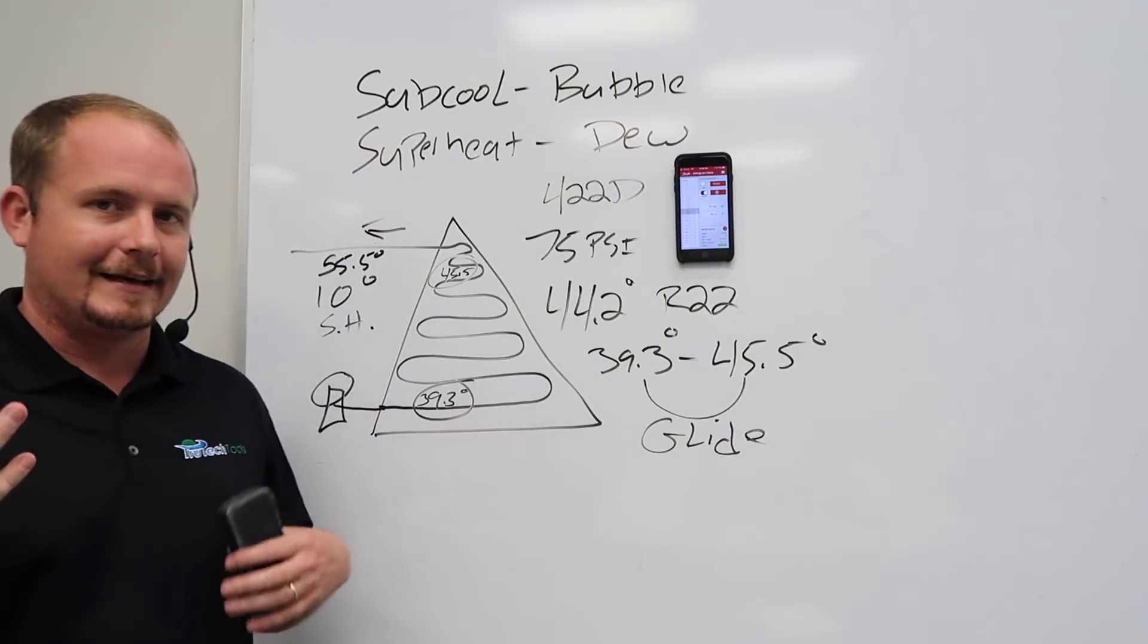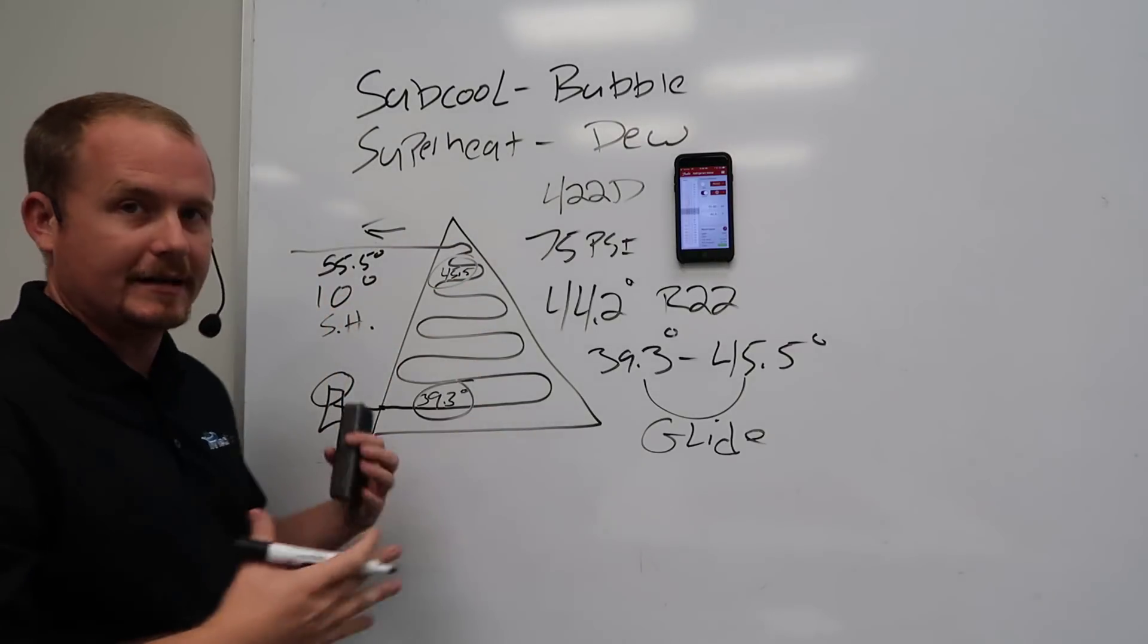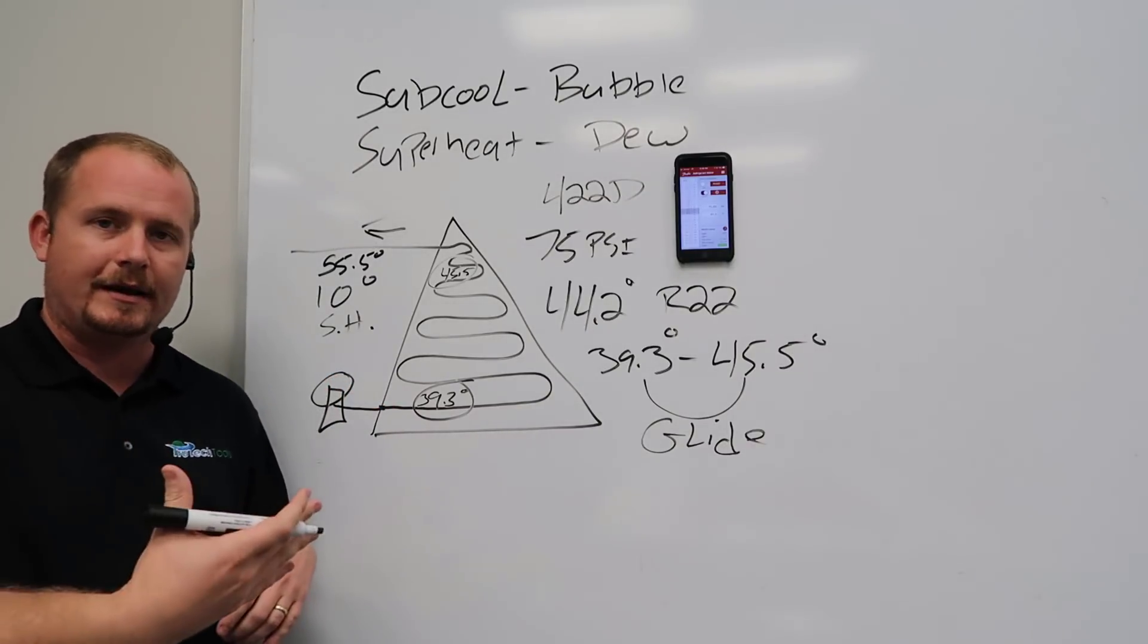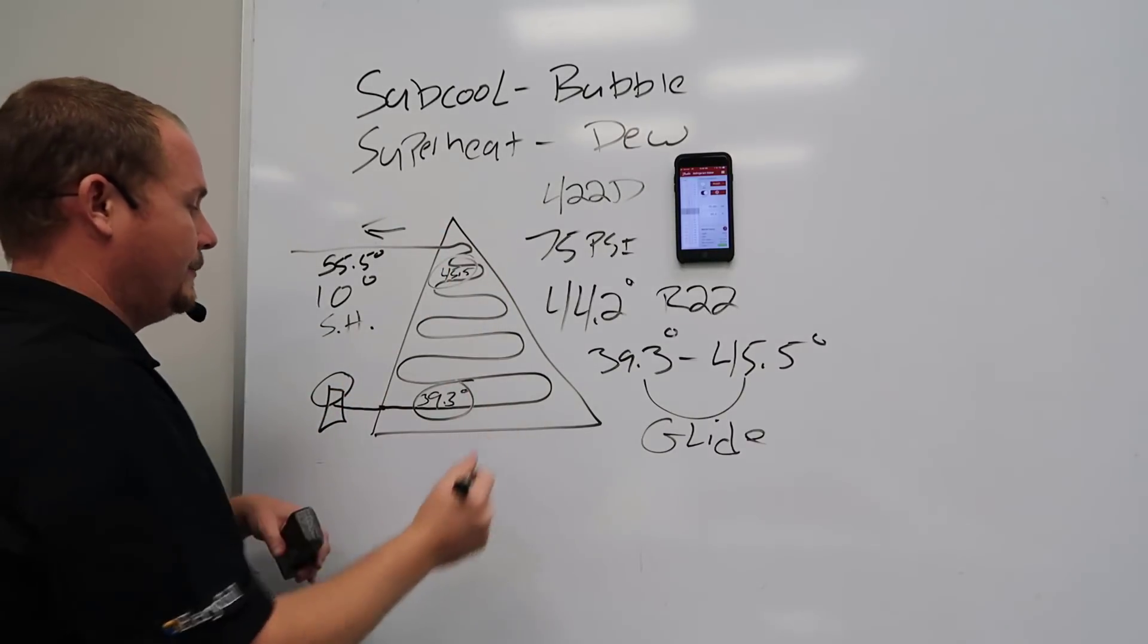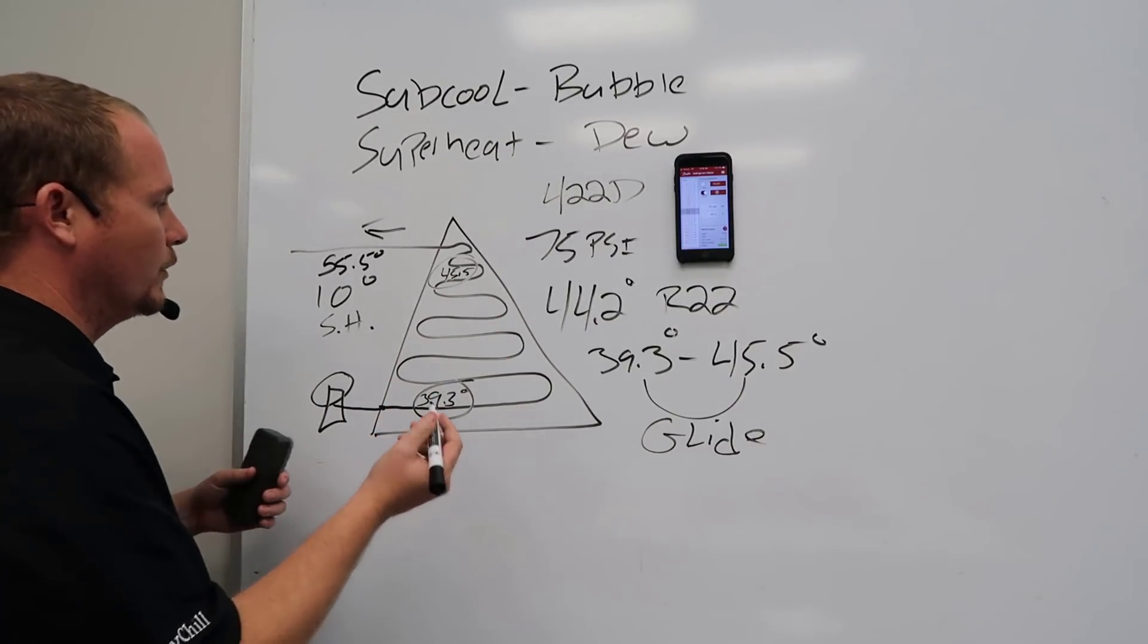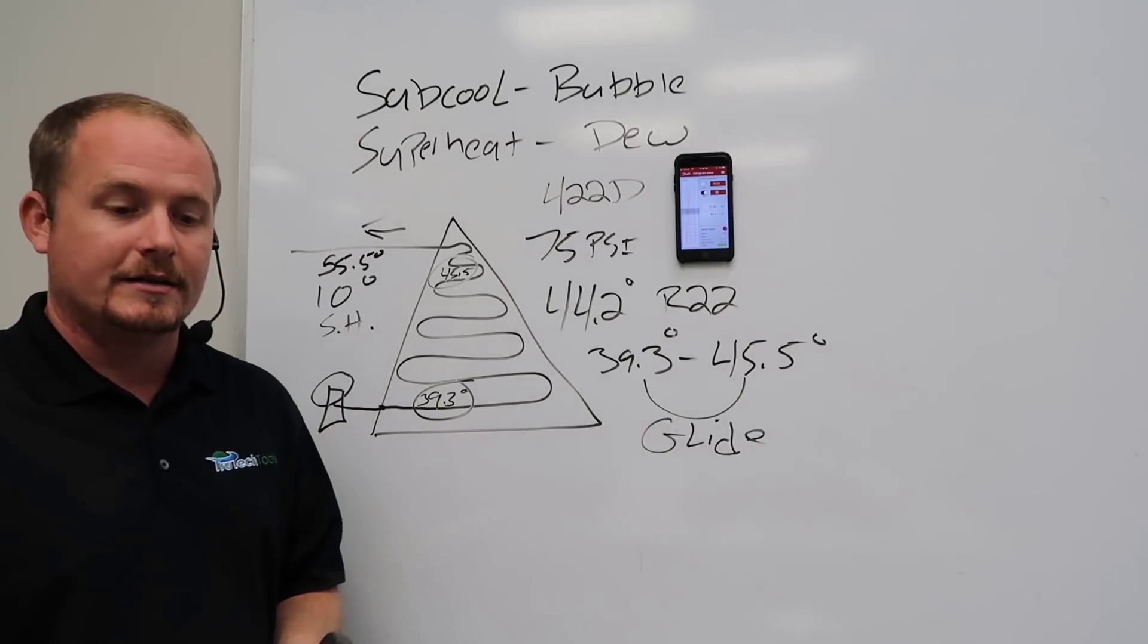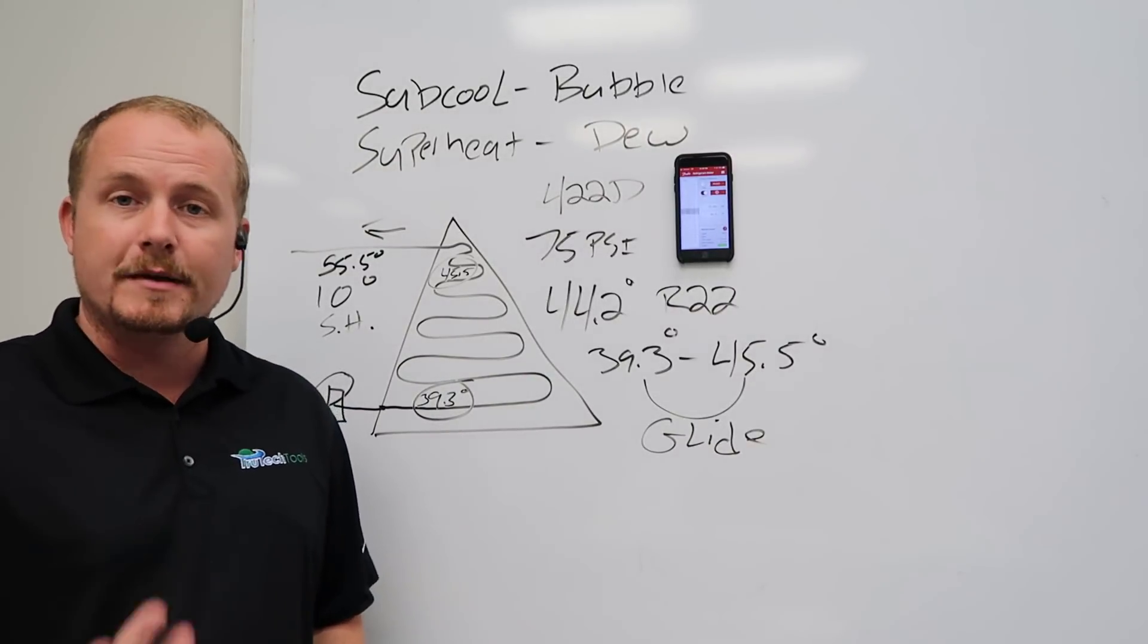But when we calculate things like design temperature difference, say if I was wanting to calculate what exactly should this pressure be based on the indoor temperature—we talk about this in the five pillars, we talk about this in checking a charge without gauges—there's a lot of cases where we want to anticipate what the pressure will be in the system for diagnostic purposes. Well, what temperature is in the evaporator coil? Is it 39.3 or is it 45.5? Well, it's both, right? So what do we do in order to calculate this design temperature difference? Or what do we actually say our boiling temperature is? This is where we come up with an average temperature, an average evaporator temperature, or average saturation temperature, or another term they'll use is midpoint.